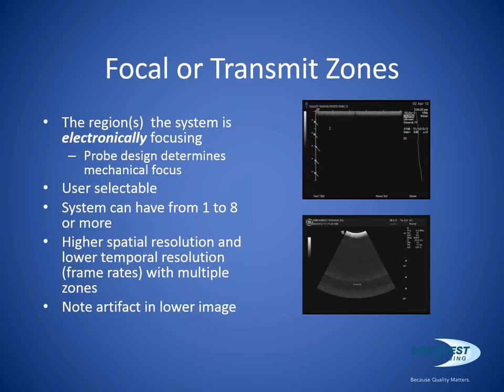We get tech support calls constantly on this, where a sonographer will see that and be convinced that their machine is malfunctioning because they've never seen that before, but it's one of those things that they have seen before, they've just never noticed it. And once they notice it, they can't get it out of their heads. So if you see a horizontal artifact that looks like this bottom image, either if you're on site, turn off multiple zones, or if you have the customer on the phone, ask them to deactivate multiple zones. If that artifact goes away, then we know it was caused by multiple focal zones. Again, it's the way the system works. They all do it, and there's nothing you can do to remedy that.